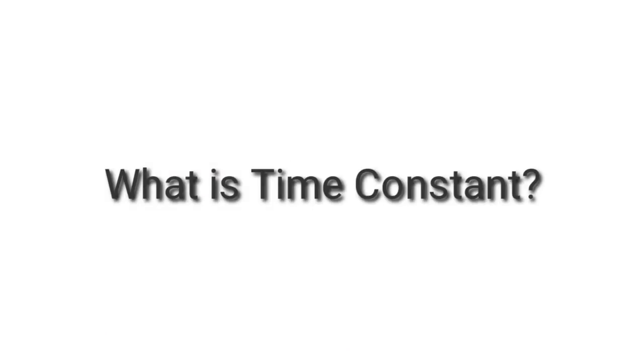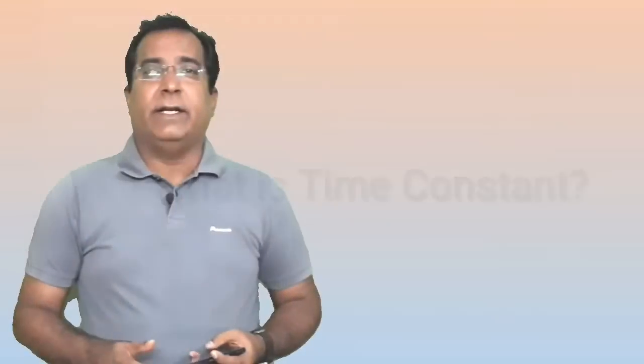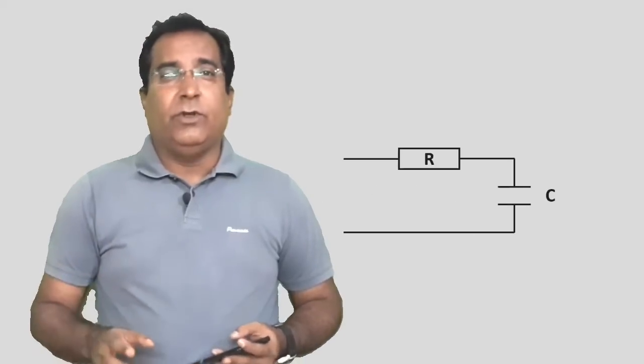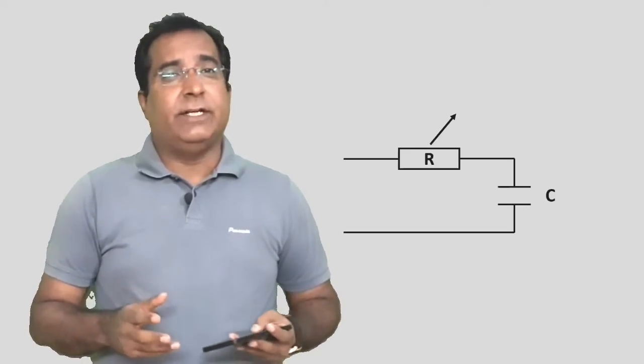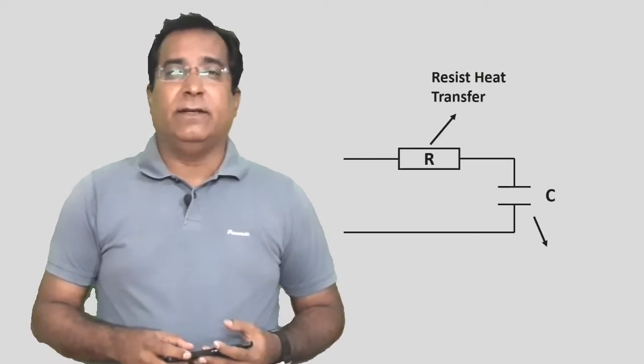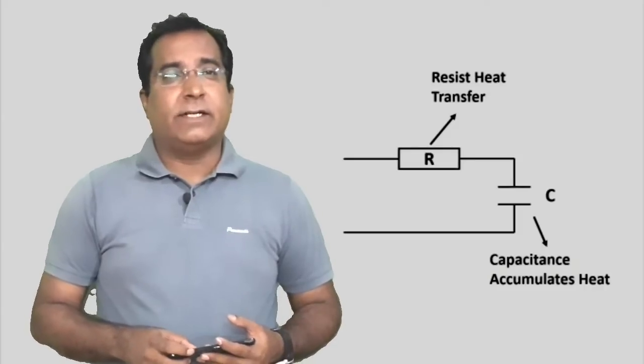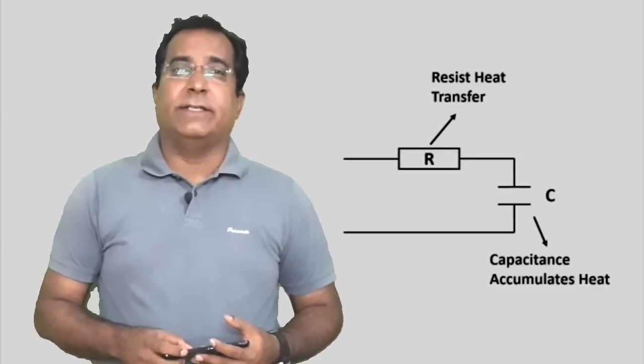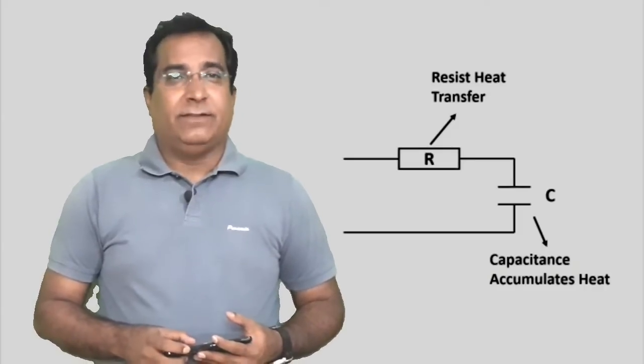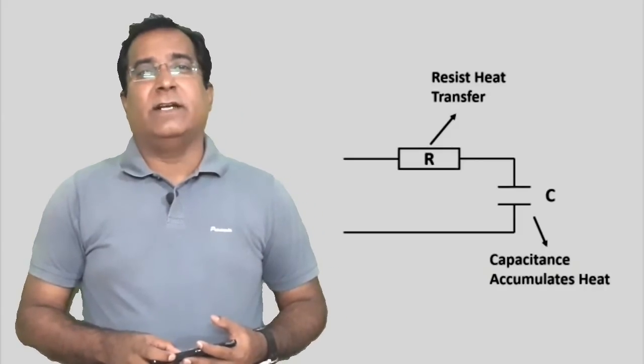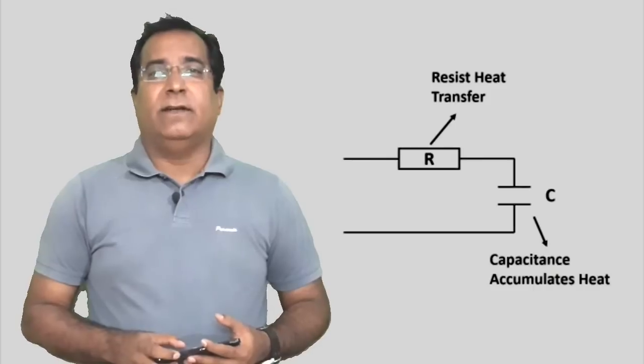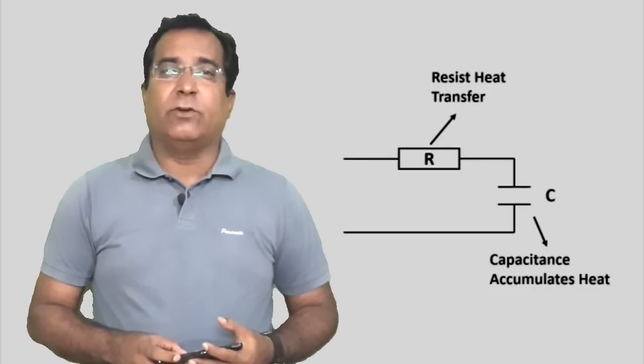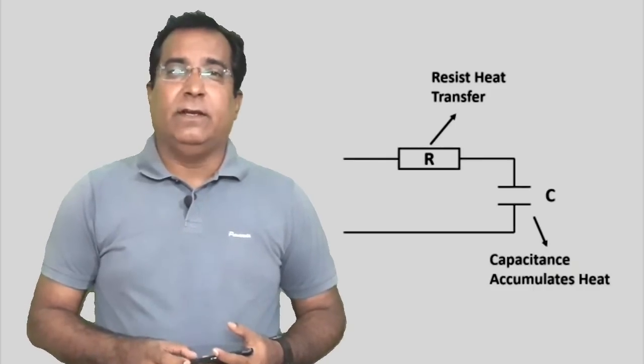Using a thermosheath on the temperature sensor adds a kind of resistance and capacitance to it. As soon as sensor is inserted into process, it does not sense at all. First outer sheath offers a resistance to the heat flow, then the sheath heats up according to its capacity. Then the temperature sensor gets its heat and sensor starts sensing. This is why the time constant of the sensor adds the delay and ultimately the response time of the control loop increases if the temperature sensor is in the PID loop.